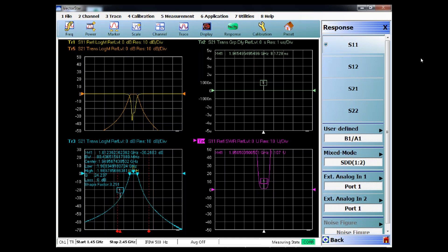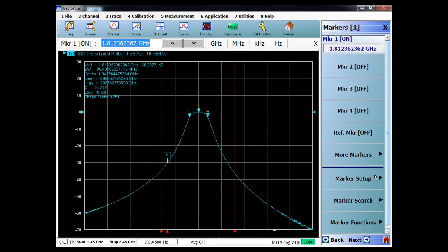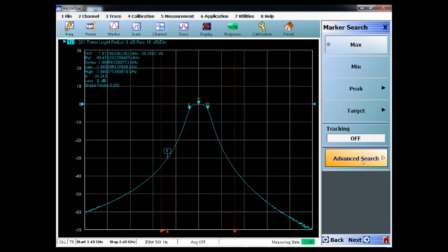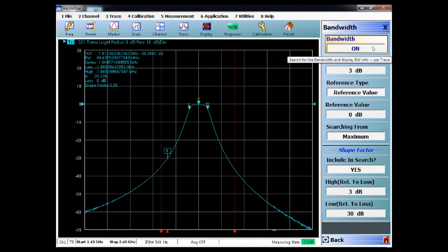Can you see my screen, Tina? Yes, I can. The VNA? Yes. So we'll look at the S21, and what you'll notice is that under markers and marker search function, go to advanced, and I'm going to make bandwidth measurements. I have that turned on, and what this is giving me is my Q-factor. For this particular filter, it's 24. And then I also have my shape factor, which is 3.251 to 1. So those are all in the benchtop models.